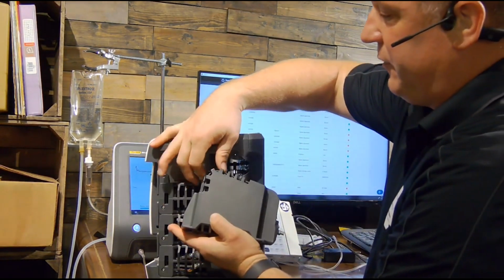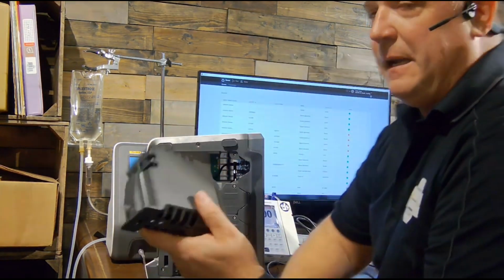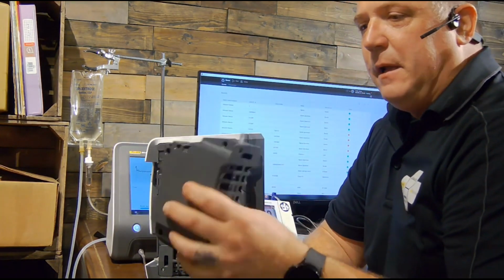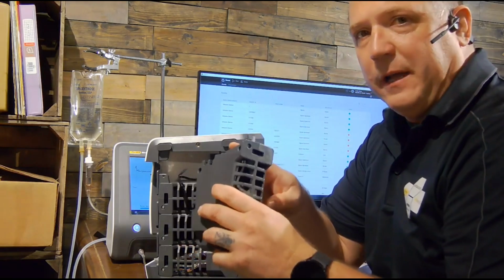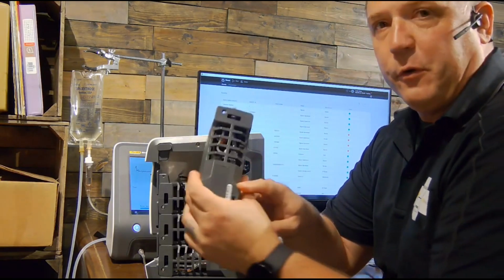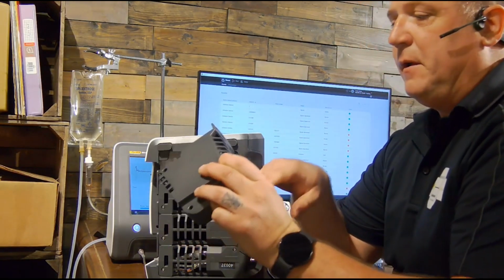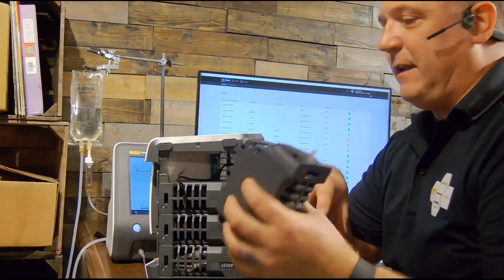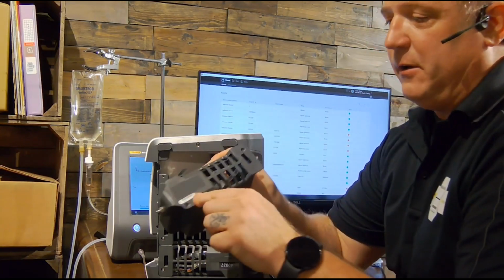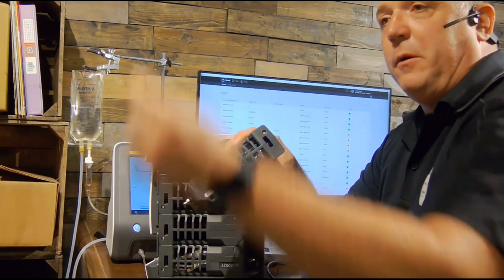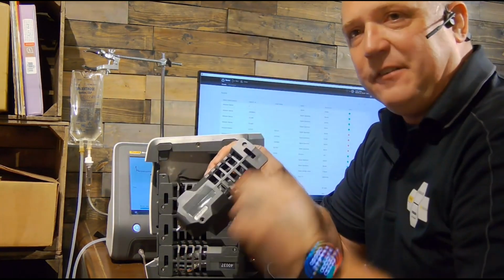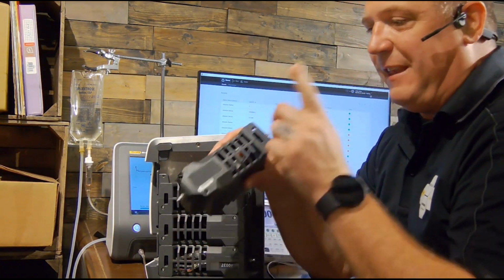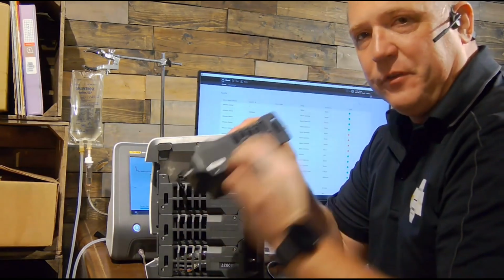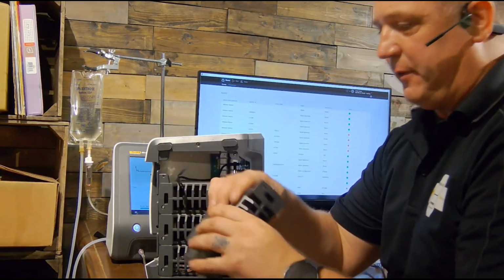I'm going to disconnect it. And this is what I sent in for calibration. The calibration is housed right on the device along with the serial number. So it corresponds to the serial number in this pump. So if I get this back and I set it into a different IV pump, it's not a big deal because this serial number will be recorded into the IDA-6 and attached to that work order in OneQA. So you know the exact channel serial number that you use for doing your tests.